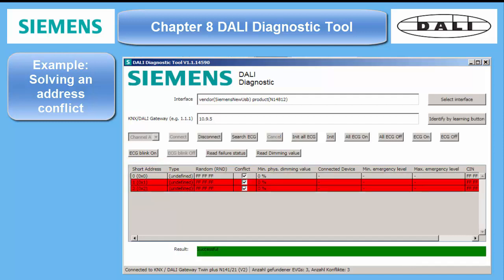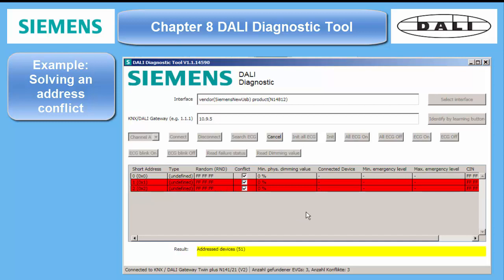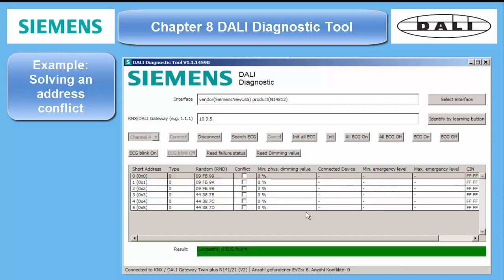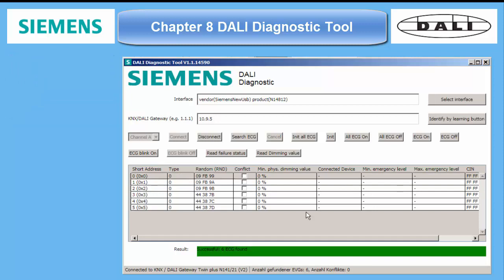With the tool or with the ETS plugin, you can clear the conflict. However, you won't be able to assign dedicated short addresses to specific ECGs — this is only possible with professional tools from the ECG manufacturers. Make sure that all ECGs are online before you start another initializing process.